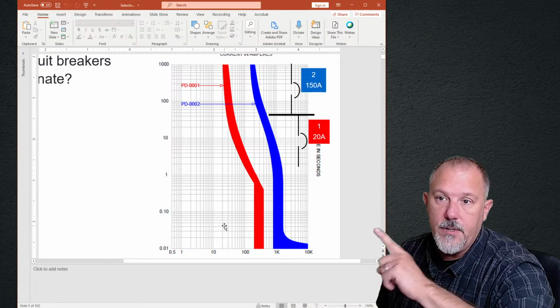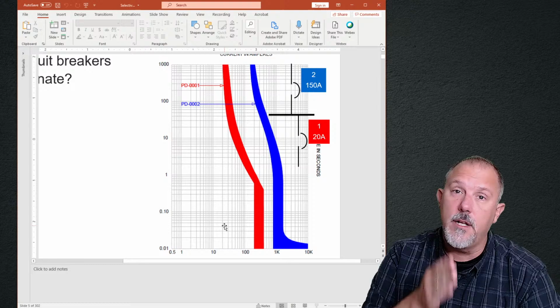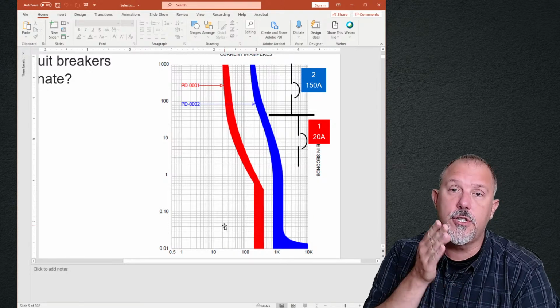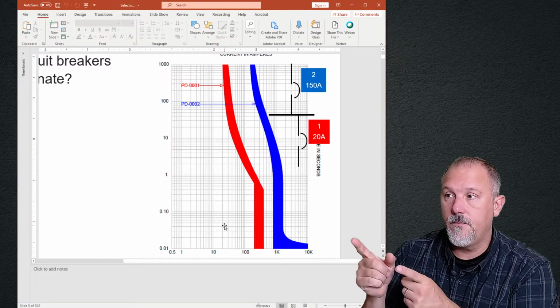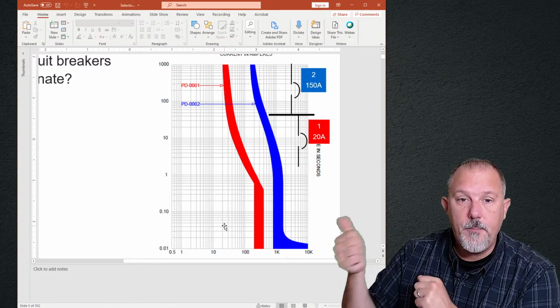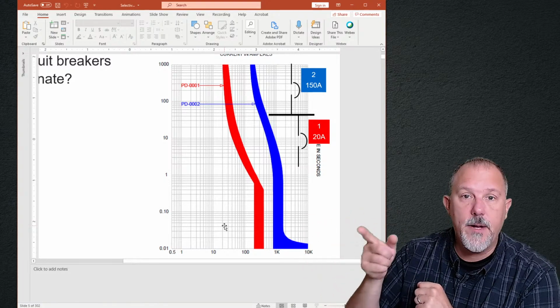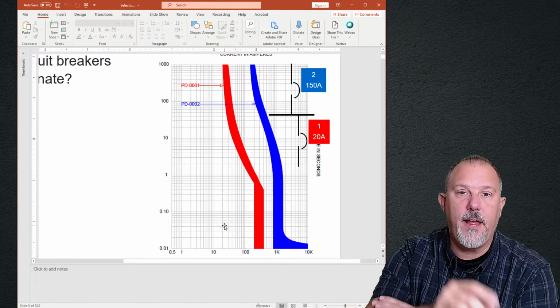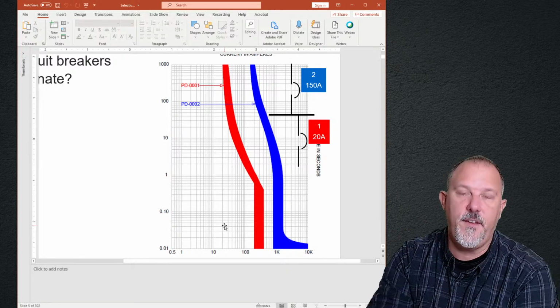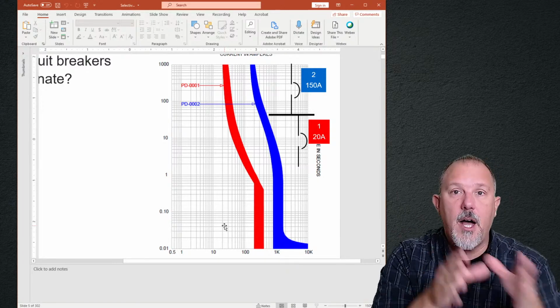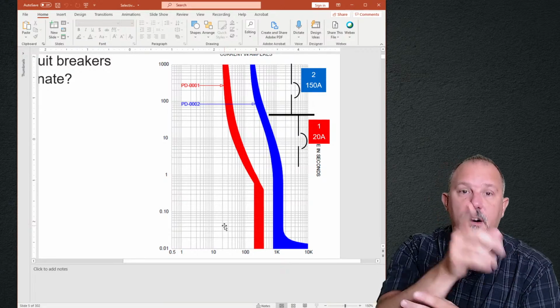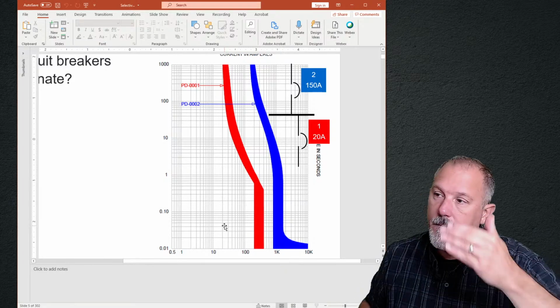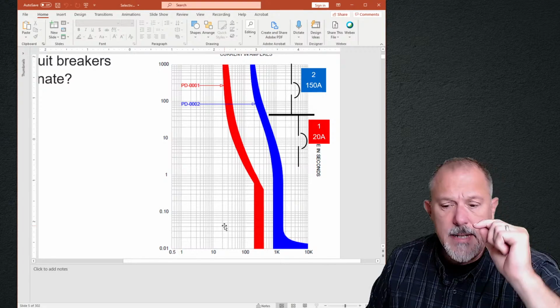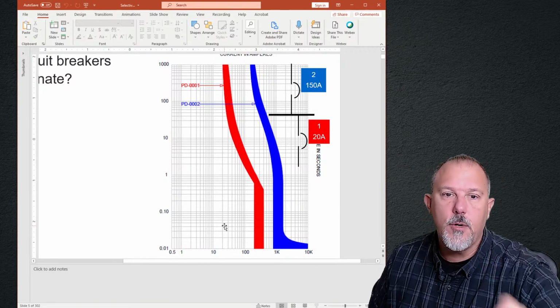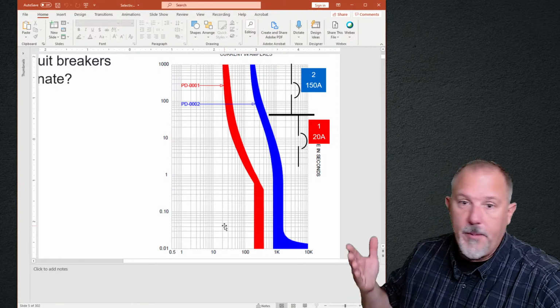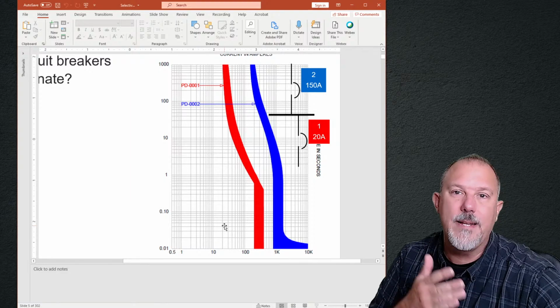Here's why I use this example. I'll tell you exactly why I use this example. I had a very good electrical engineer, very, very smart individual, send me this curve, which is a BAB. This is our BAB breaker. This red circuit breaker is a BAB 20 amp breaker. And the 150 amp breaker is an F150, not the truck, the breaker. So it's an F frame 150 amp breaker, which is upstream of the BAB 20. And they sent this image, this TCC curve, and they said, wow, look at the great selective coordination of these two breakers. Because look, I mean, you got separation all the way down to 0.01 seconds.